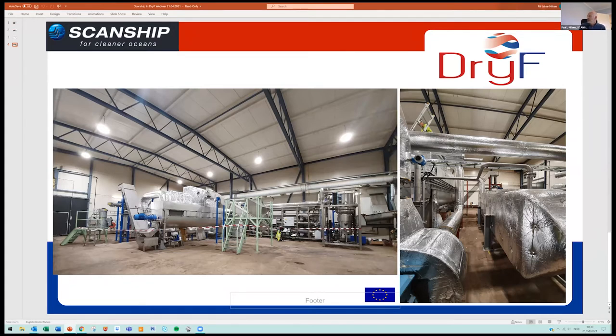So this is a picture of sort of the main elements of this superheated steam dryer. You could see our dryer, a guy on top is doing some modifications. On the right, you have the heat exchanger we have developed with easy access, so we can go in and wash it out if it is accumulating dust in this case. And then you have the fan running with large pipes to circulate the steam.